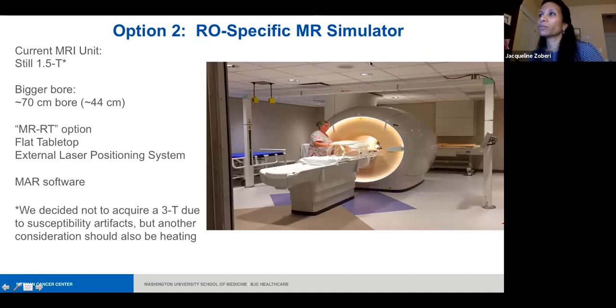Option two would be you acquire a radiation oncology specific MR simulator. This is actually what we got six years later after inheriting that old scanner, and that was quite nice. We stuck with the 1.5 Tesla, got a bigger bore, and the flat tabletop and lasers came standard with the system. We also got some metal artifact reduction software, so it was a pretty nice upgrade.